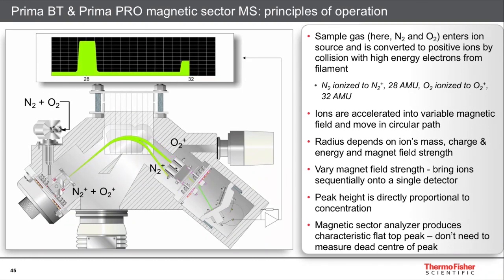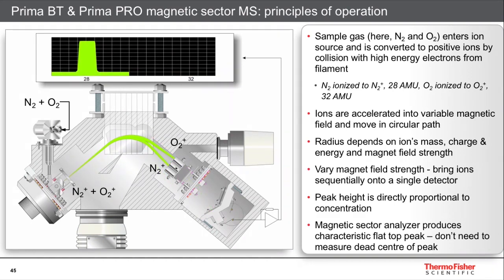The third component is the detector — conventionally a Faraday detector — where the peak height observed is directly proportional to concentration. This is the most precise and reliable method for monitoring off-gases from fermentation processes. It should also be noted that this type of mass spectrometer is routinely employed for monitoring multiple fermenters or bioreactors — by combining a scanning magnetic sector mass spectrometer with a multipoint inlet, a single spectrometer can monitor many process sample points.